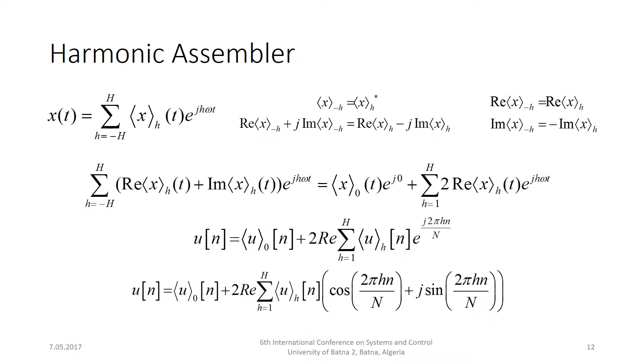We applied the algorithm with the STM32F4 Discovery board with an ARM microcontroller and sent the reference signal and PI parameters from a computer with MATLAB via serial port. The controller requires these signals and listens for them from the serial port after powering up. When the required signals are received, the microcontroller begins the harmonic control arrays method. It takes the error signal in a sliding buffer, disperses it sample by sample, applies the required control process to each harmonic component, assembles the control signals, and applies them to the plant with linear mapping. This process continues in an infinite loop.